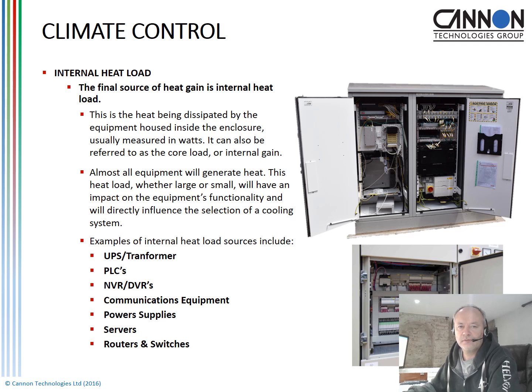Heat load, the next source of heat gain, is internal heat load. This is the heat produced by the equipment that's been installed. Obviously, any power to equipment is going to turn into a heat load of some kind, and we need to understand what that heat load is. If you don't have that information from your equipment supplier, we'll look at the amount of power that piece of equipment will utilize, and we'll turn a percentage of that power into heat. All equipment has an efficiency rating, and the efficiency allows us to work out the heat load of that equipment. This is referred to as the core load or the internal heat load from the equipment.